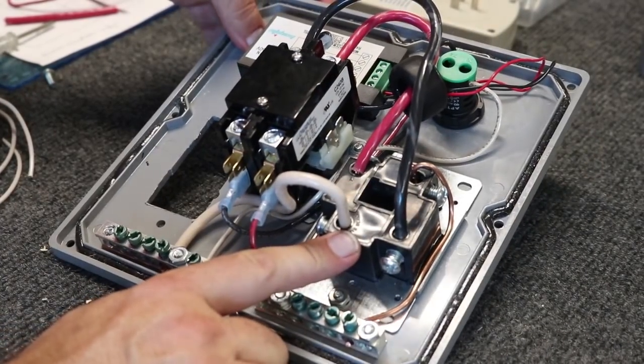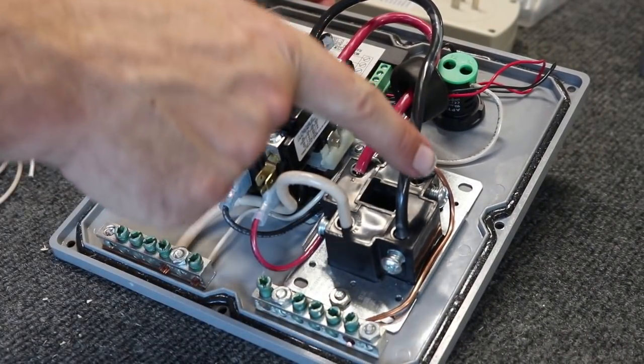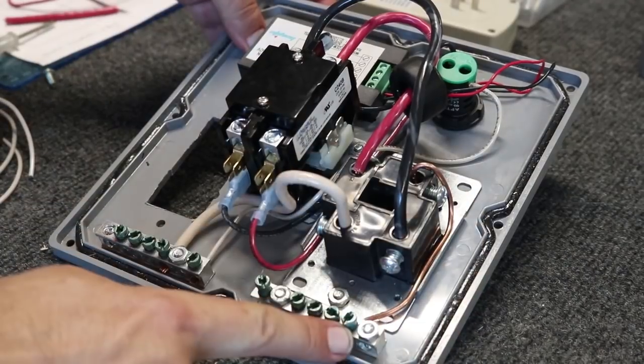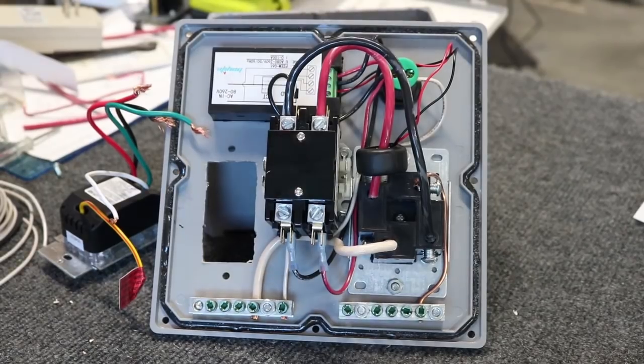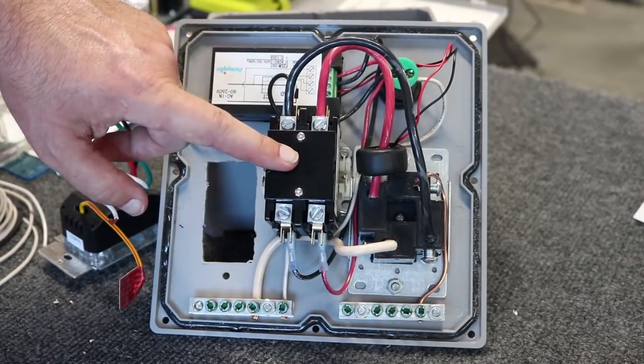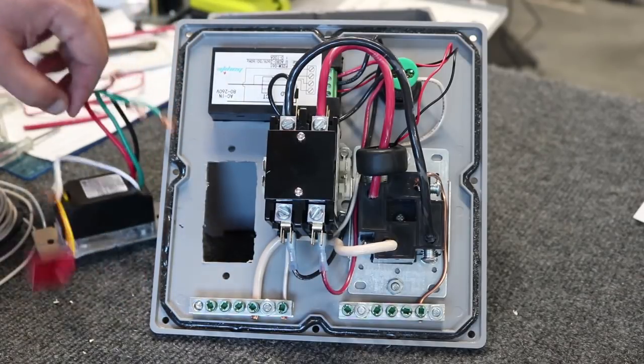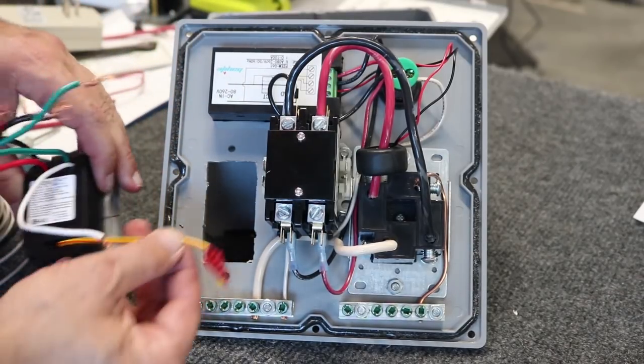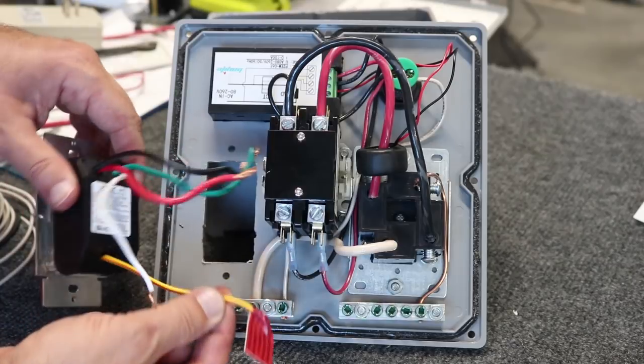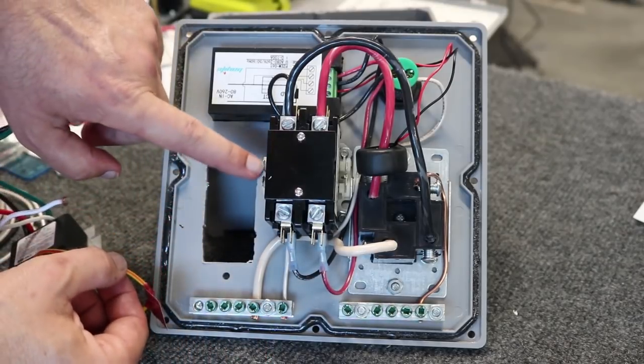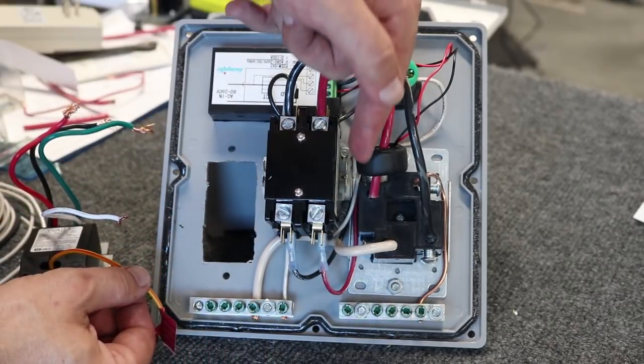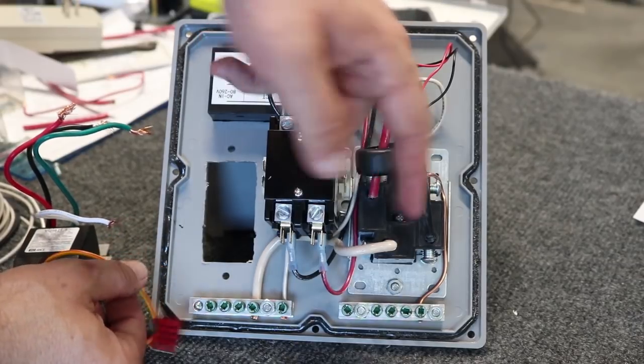So now the NEMA 14-50 has hot, hot, neutral, and ground. On the contactor, it's a 120 volt coil. So what I'll do is use the hot switched output from the smart switch here onto this connection, and the other end of the coil, just a neutral wire back to the neutral bus to complete the circuit.